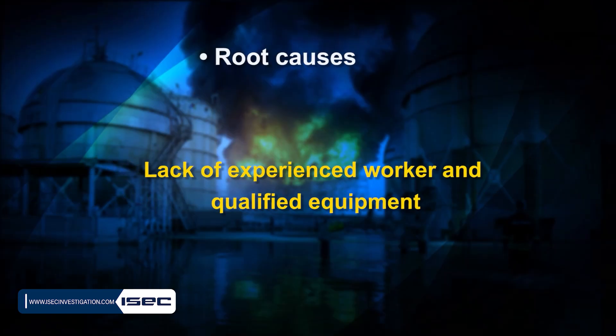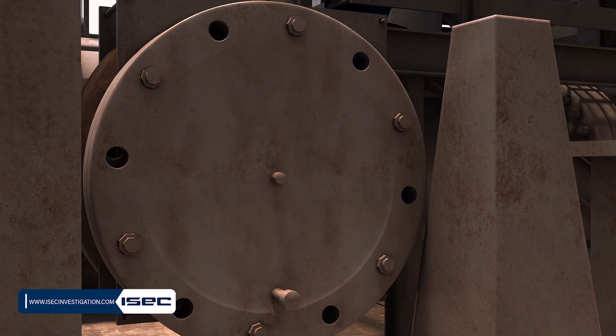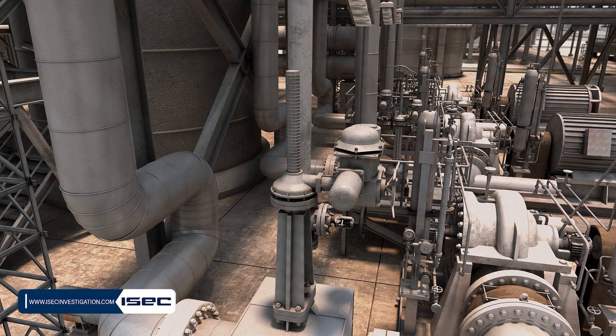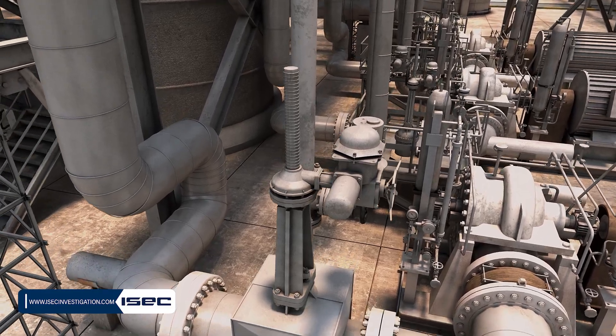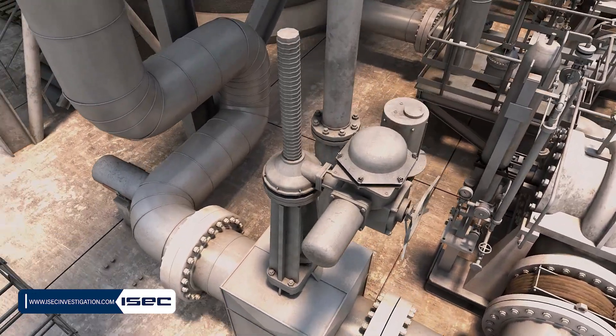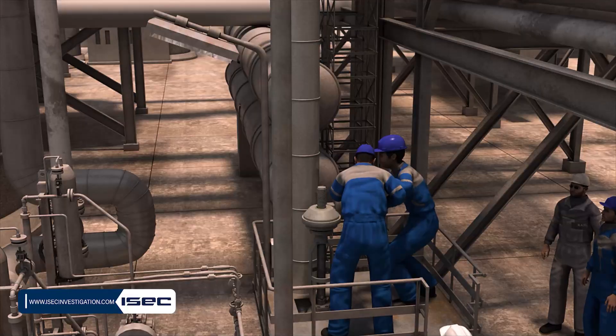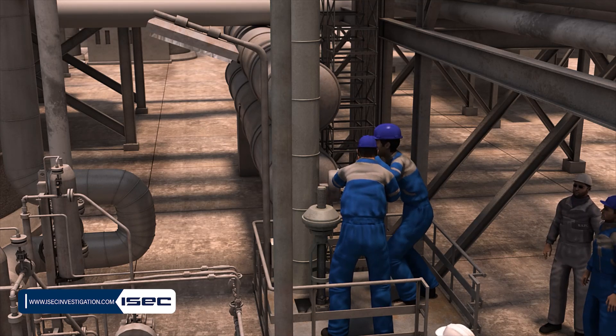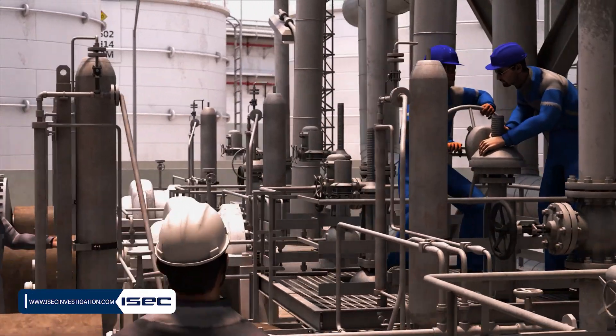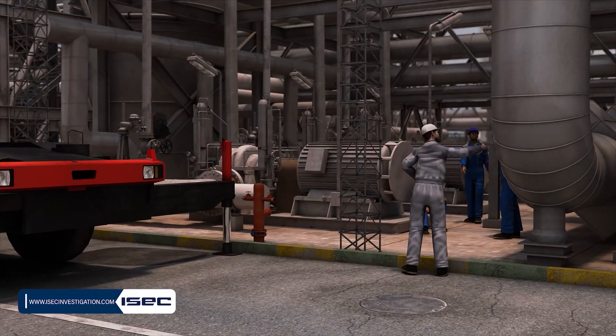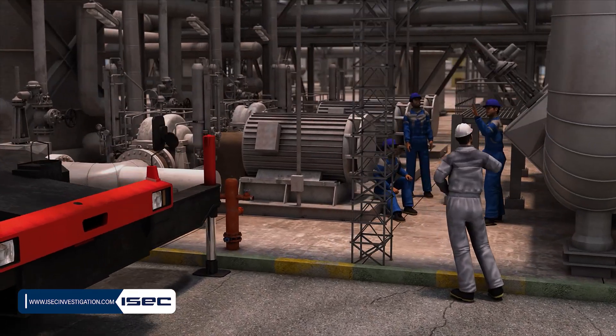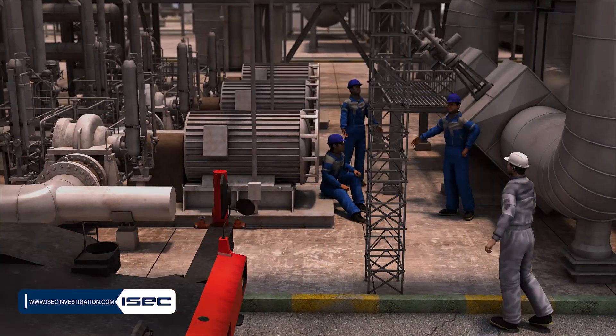Lack of experienced workers and qualified equipment. The use of handmade blind flanges in this complex had become quite common, and the electrical gearbox motor could not be adjusted to close the valve completely, and there were not enough manual gearboxes for all valves. The use of inexperienced and unskilled repairmen for cost saving is another example of this root cause.